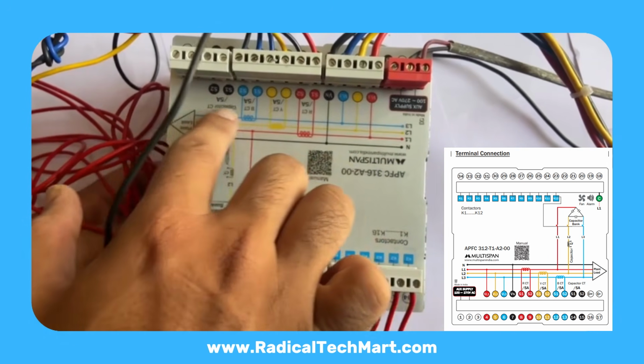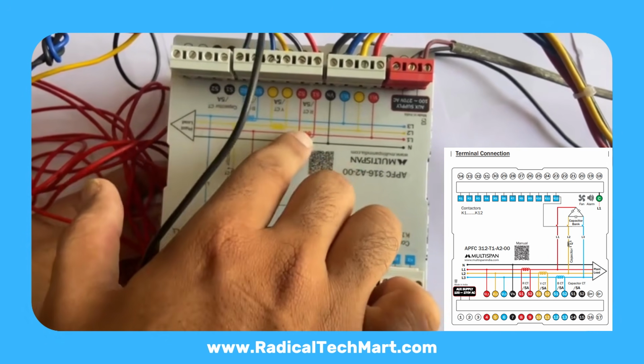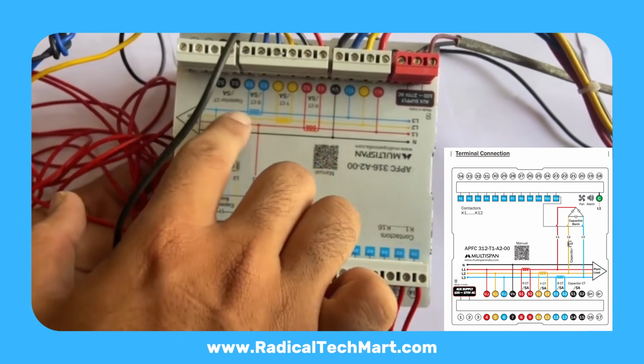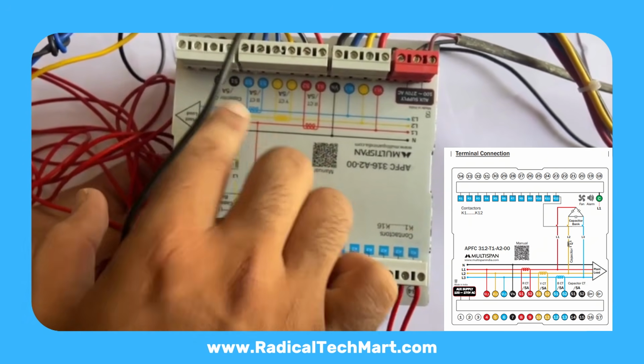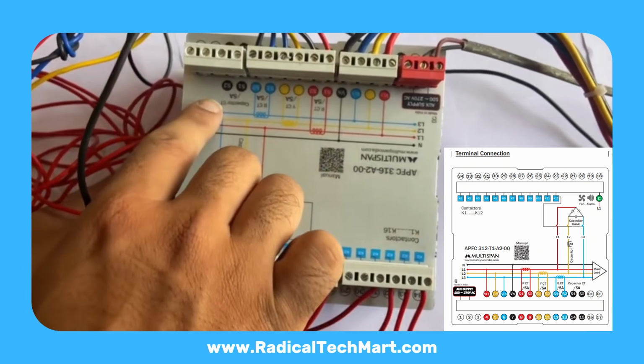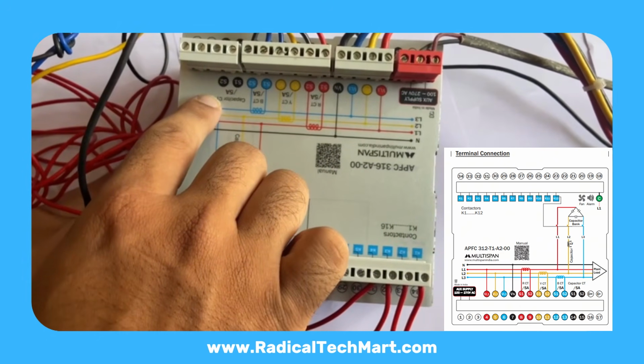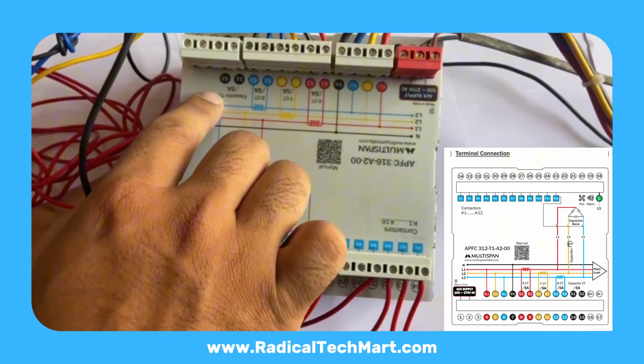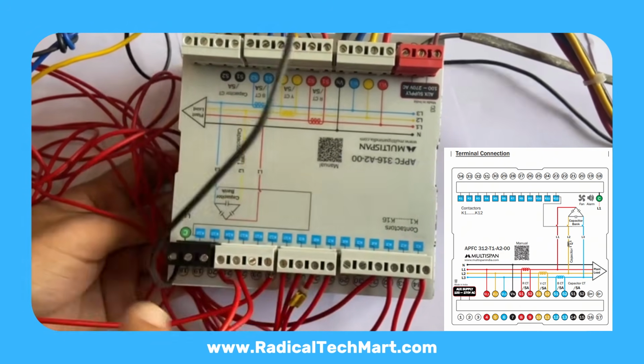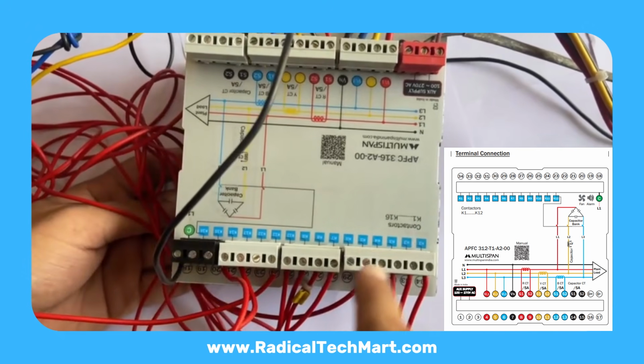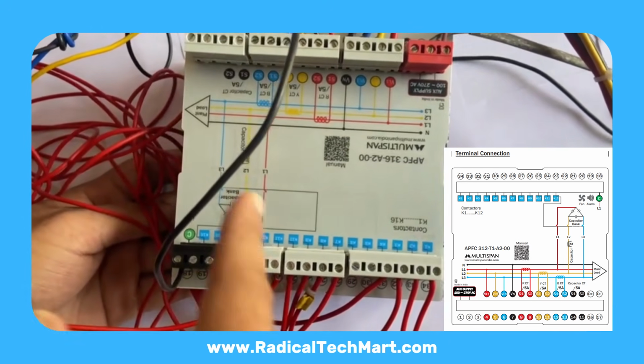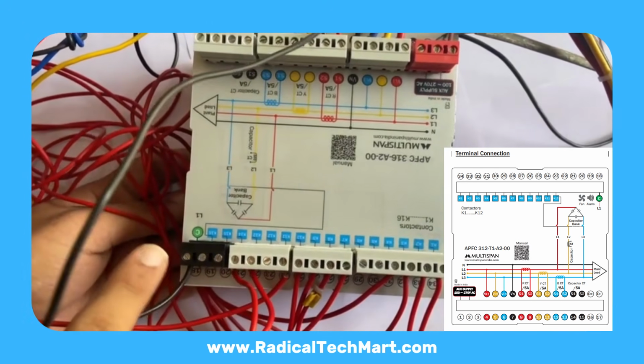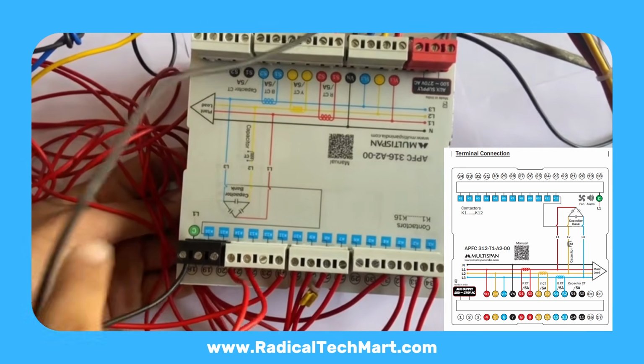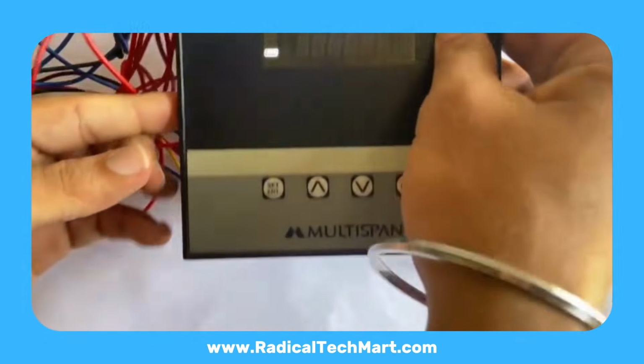The next terminals are for your CT connections: R phase CT, Y phase CT, B phase CT. And on this side, you have the capacitor CT terminals marked as CA, CB, etc., where your capacitor side CT wires will be connected. At the bottom, you have the relay contact terminals. The common terminal is provided here, and from there you can connect your capacitor bank contactor coils.